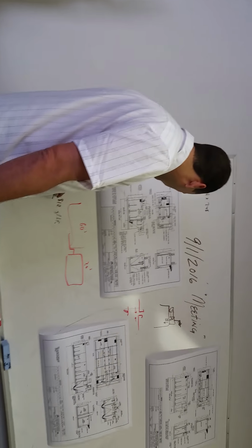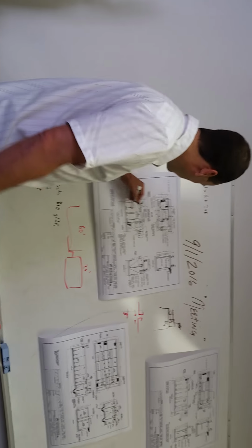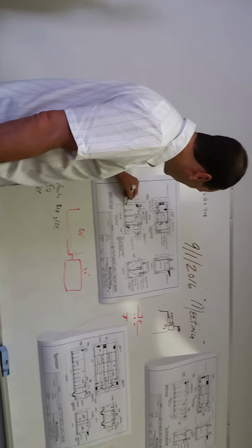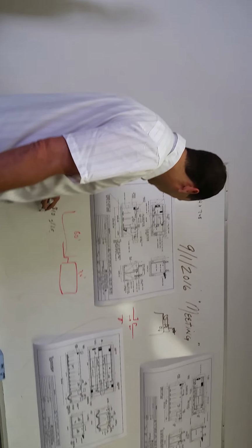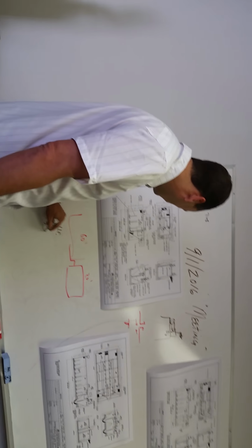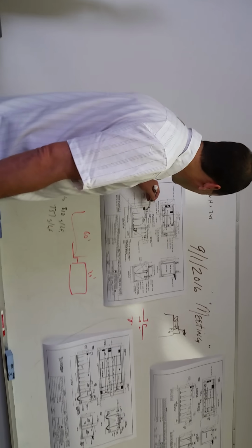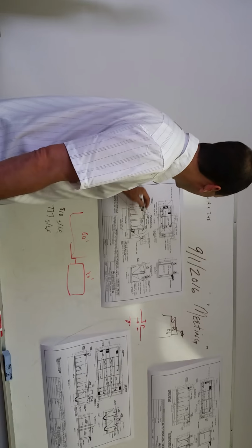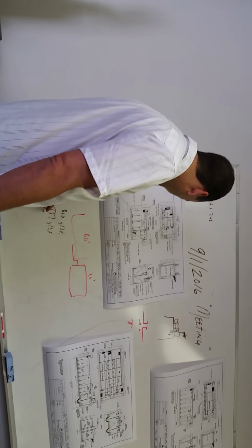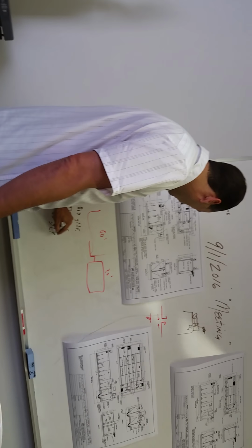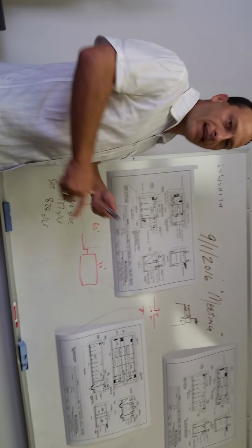Or the same tank, because we don't take into account the bottom 1 foot, which we keep full to keep the pumps cool, is 737 gallons per linear foot. And the sludge holding tank is typically a little bit deeper because we want to overflow back in with the supernatant. That tank is 828 gallons per linear foot. And we have those tables for all of our different widths and heights.